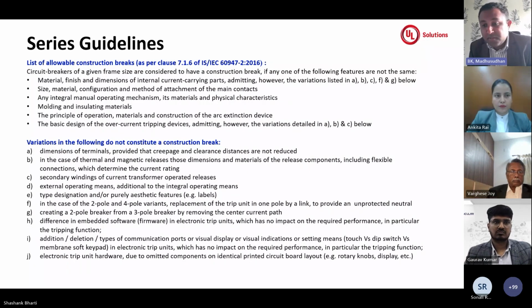And your molding and insulating materials should be the same. For each rating, you cannot use different molding materials. So basically it is on the plastic part. So your complete range should have a single plastic part. If there are different plastic parts, then you should treat them as different constructions and include them in your construction breaks. And also the principle of operation, materials, and construction of arc extinguishing devices must be the same and of the same design. If you see any changes within the construction, then you need to treat those as separate constructions to consider for test plans.